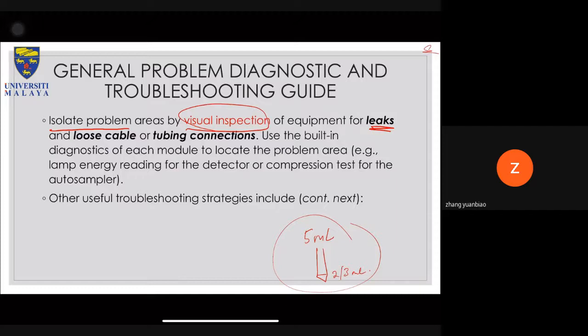And of course, if there is a leak at a particular place on the HPLC, normally the manufacturer puts a leak detector in the system, whereby if the leak is excessive, the system will stop running altogether. Okay, so why does the system stop? Because sometimes if you are doing an analysis, you don't do it between 8 to 5. Sometimes you run the system for 24 hours non-stop. So if there is a leak in the system, say at 12 midnight, the system will stop pumping and everything will stop, and therefore you can save solvent, avoid flooding, and avoid other mishaps, for example electrocution or fire from short circuits and whatnot.